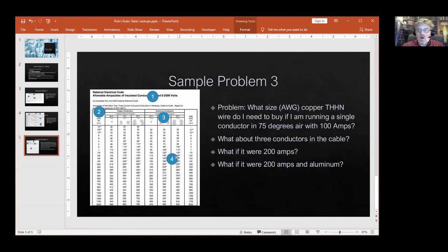You can't round down with wire, you don't want to have less ampacity, you want at least equal to or greater. So the next size above 200 amps is 205 and I slide that over and now I need wire size 250. So if I'm running 200 amp service for a building and I've chosen aluminum instead of copper I will need wire size 250.